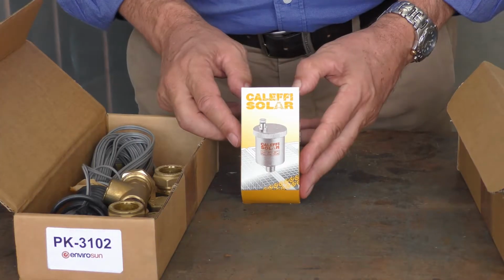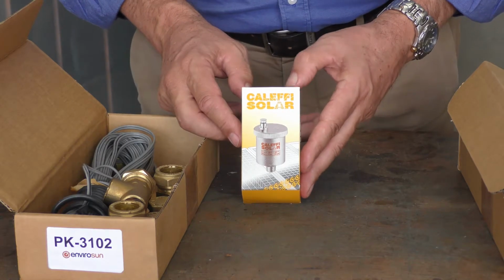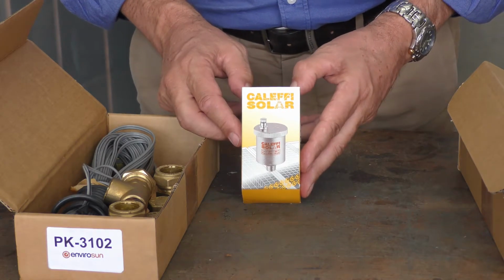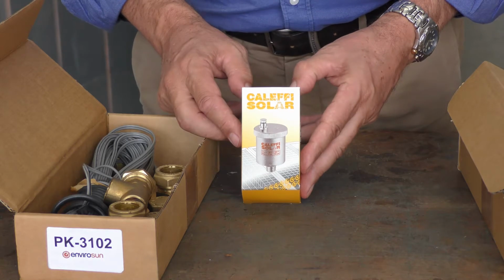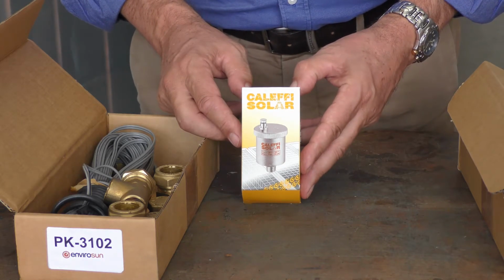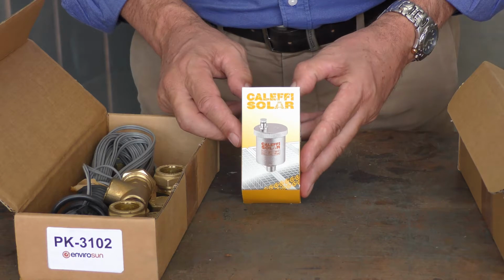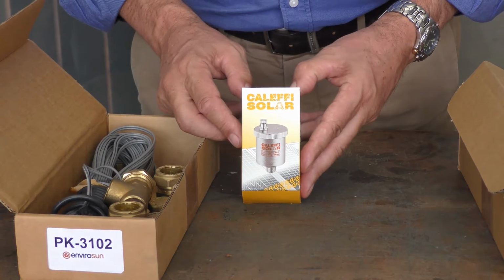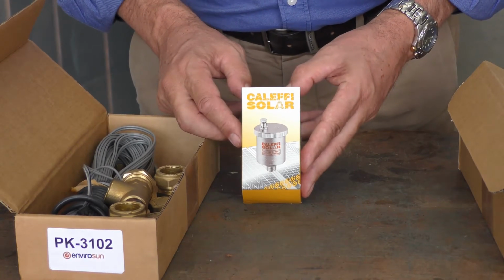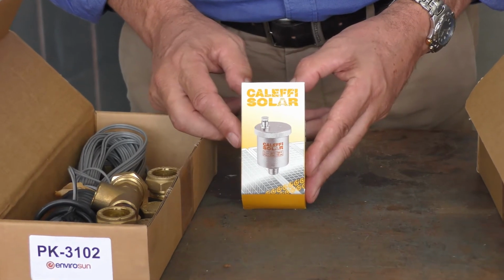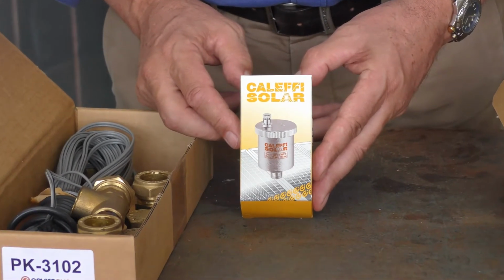I mentioned before, this is the Caleffi Solar air vent valve. It's a pretty important part of our system. It allows the discharge of gases and air that get trapped in the system at the very top of the collector where they percolate to or can accumulate. Without this, your pump can cavitate and not be able to circulate properly.